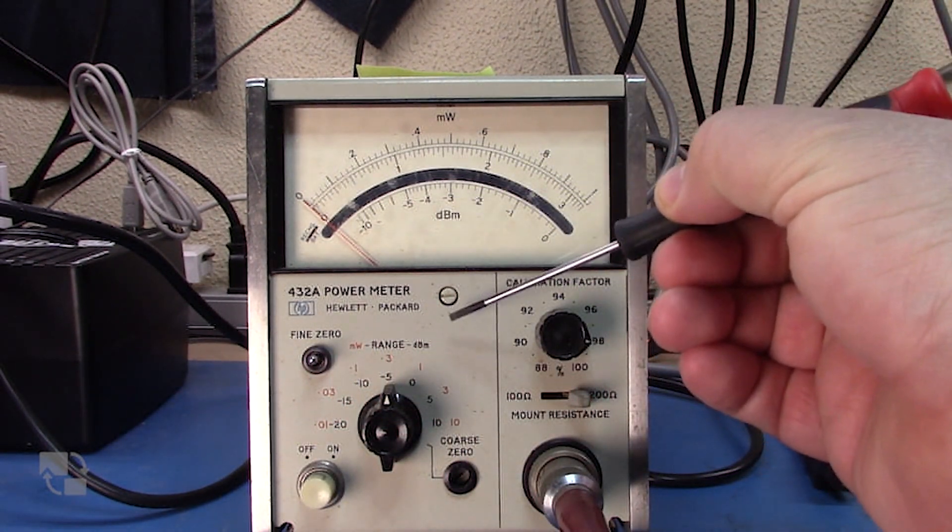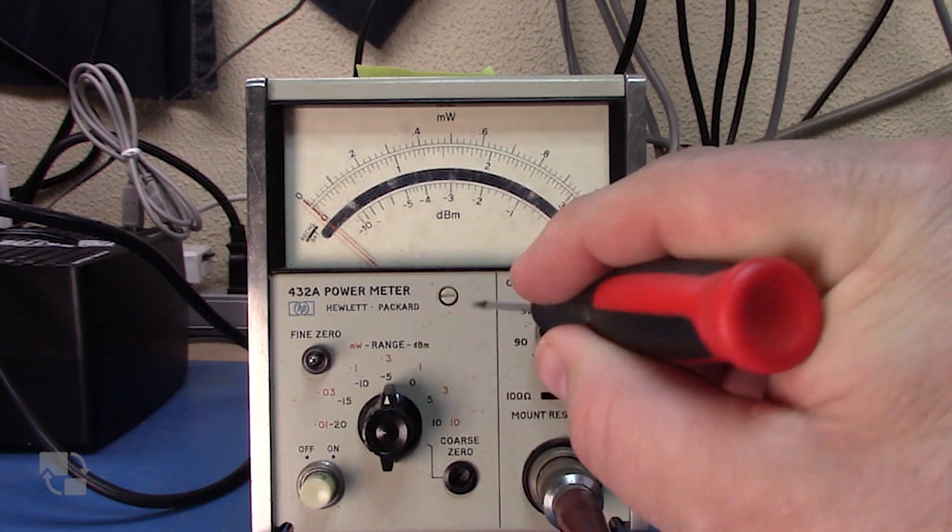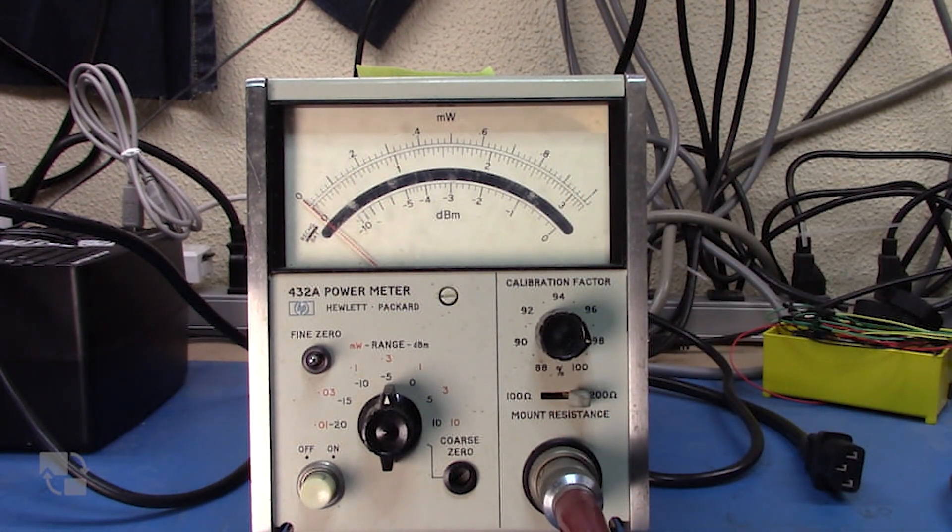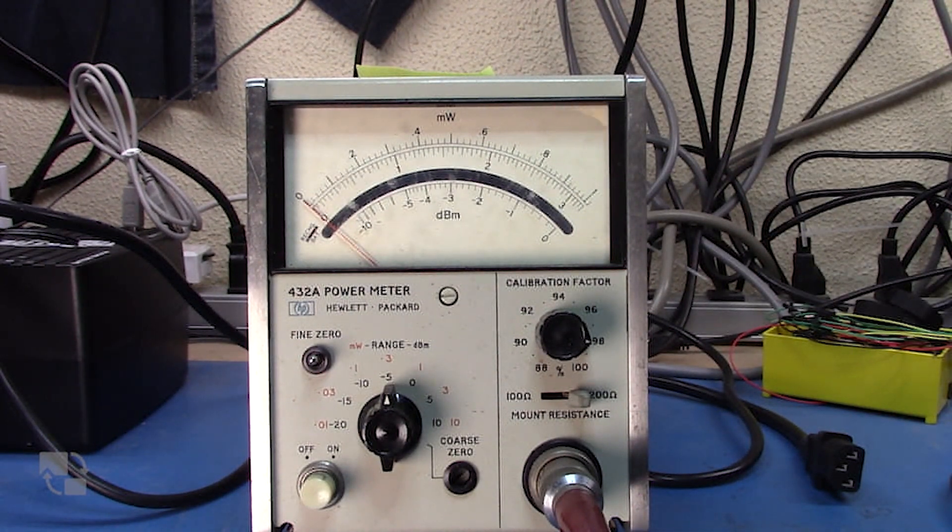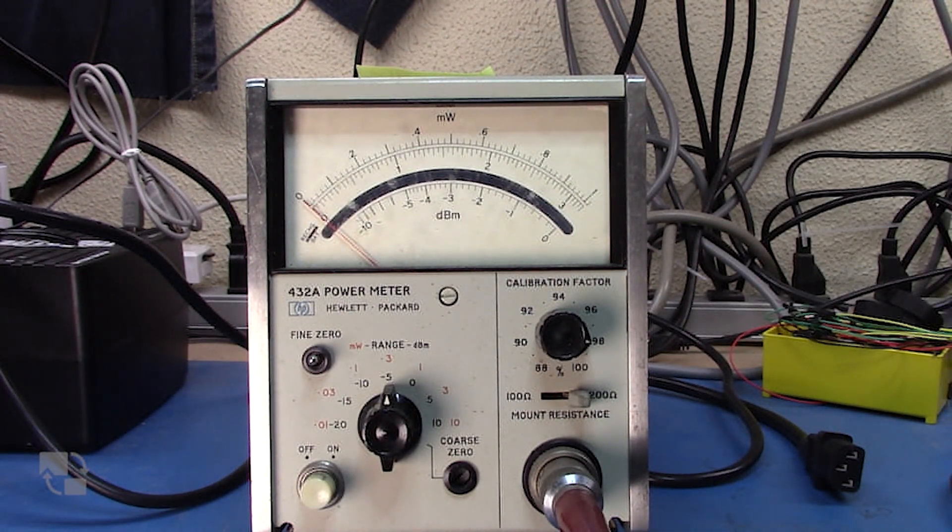Now, how this works is there's a little slot in there. And this item, this screw basically has a pin in that slot. And that's how it sets the meter zero. And so you want to back it off a little bit to free it up to make sure that the meter can turn and isn't being driven by that set.